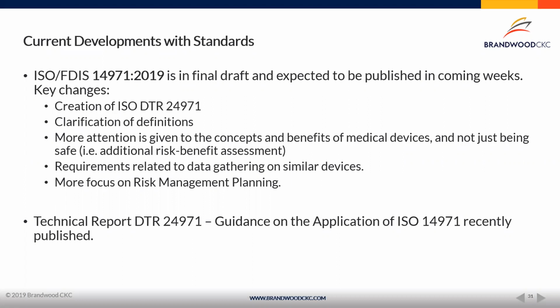So you now have a document that really shows you how to apply the 14971 standard to your medical device outside of the standard itself. Next one, beneficial to industry and manufacturers, is that they've clarified a lot of the definitions around 14971. So as we talk about harm, hazards, risk analysis, controls, mitigations, things like that, those are all things that have been clarified in the definitions for 14971 as part of the new revision.